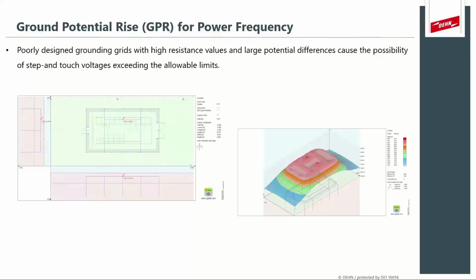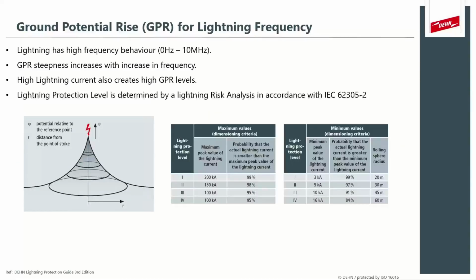Now that's the challenge with lightning. Lightning creates an extremely high voltage gradient. And that's why a system that is designed to be safe for 50 or 60 hertz at power frequency might not be safe against lightning frequency. As you remember in the white paper I explained previously, we spoke about 25 kilohertz, 250 kilohertz, and it goes up and up. And lightning is known to have high frequency behavior, and it can change from DC up to 10 megahertz in microseconds even. And that creates a very high ground potential steepness.